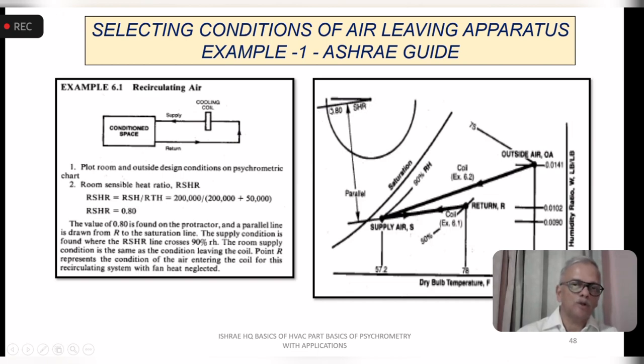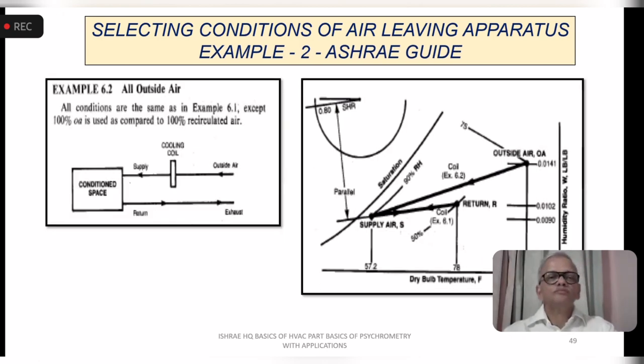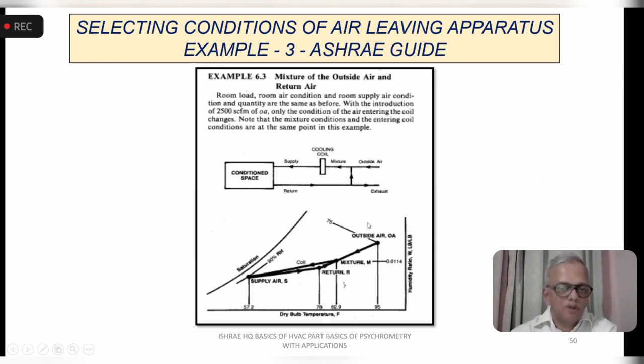So that is the sensible heat ratio line, parallel to that, passing through the room. And that's where the 90% RH line is. This is ASHRAE style, so it is assuming that the coil will saturate the air up to 90%, not 100%. And that's the point taken for the air leaving the apparatus, or the supply air condition. This is all outdoor air, which we saw, 100% fresh air over the coil gets here, and then that is exhausted. The same chart is shown here. This is the mixture, which we have seen before, and that is a psychrometric process which we have already seen. So we have a mixture of return and outdoor air, the mixture condition going over the coil, and supply being at that 90% RH from the coil.